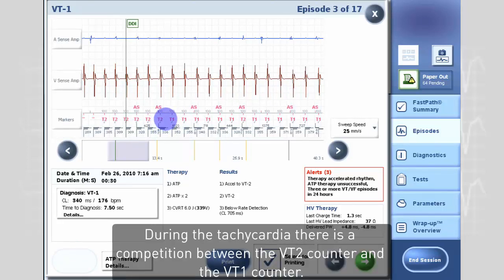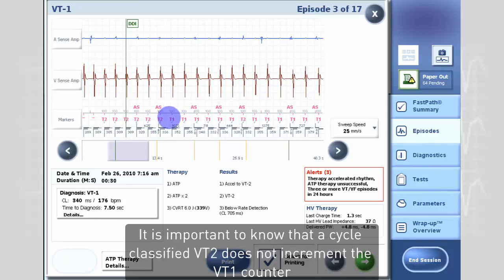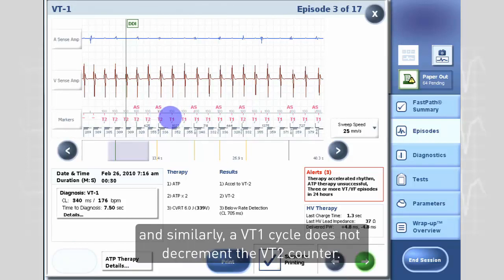During the tachycardia there is a competition between the VT2 counter and the VT1 counter. It is important to know that a cycle classified VT2 does not increment the VT1 counter, and similarly a VT1 cycle does not decrement the VT2 counter.